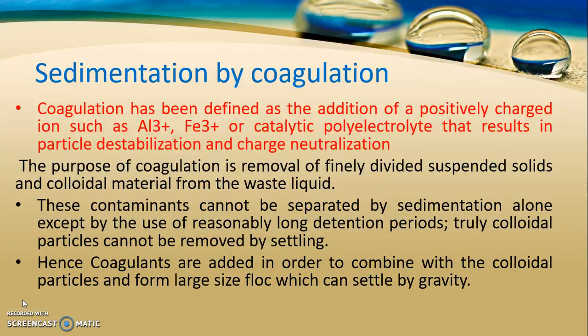After plain sedimentation, the next step is sedimentation by coagulation. There are certain particles which do not settle down on their own in sedimentation tanks. These suspended particles that do not settle by themselves possess some negative charge and are always in suspended motion in the water — they are called colloidal particles.